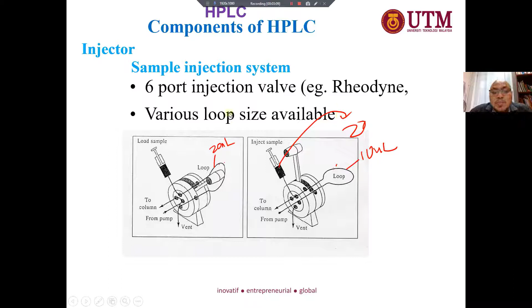Here is how the sample load and injection work. The sample injection valve introduces the sample quantitatively onto the column without interrupting the mobile phase flow. So the Rheodyne 6-port injection valve system is kind of magic, where you can introduce the sample into your mobile phase without stopping or interrupting the mobile phase flow. That is the magic of the sample injection valve. Okay, how does it actually work?